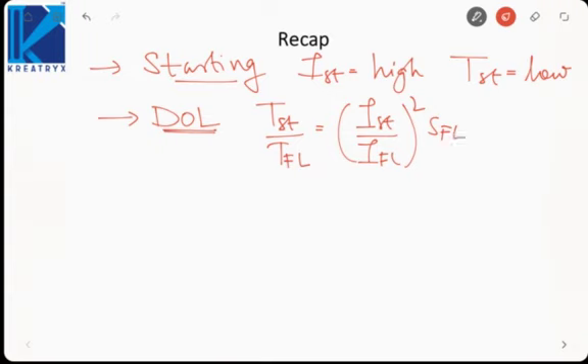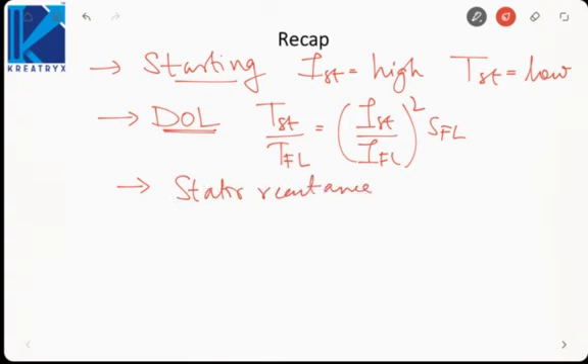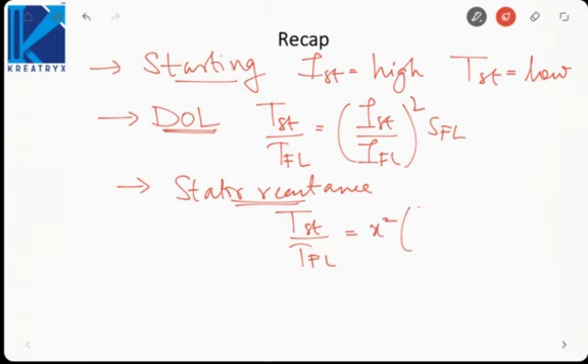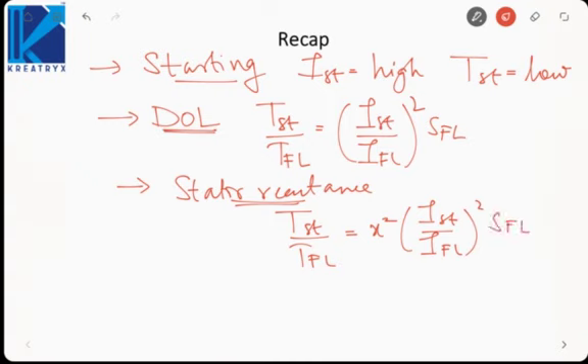Then we saw the reduced voltage starting method. First was stator reactance, in which we use a potential divider to reduce the voltage at the stator terminals. The starting torque to full load torque was given by x² × (I_starting / I_full_load)² × S_full_load, where x was the potential division ratio applied across the stator winding using the potential divider.